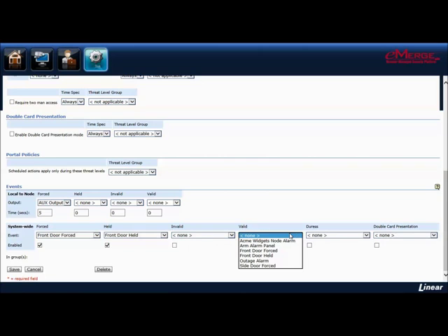The portal will trigger the valid event when a valid access has been performed at the portal. Take note, the event is only triggered on an access completed. If you have a door status monitor programmed for this portal, it must go in and out of alarm to alert the system the access has been completed.